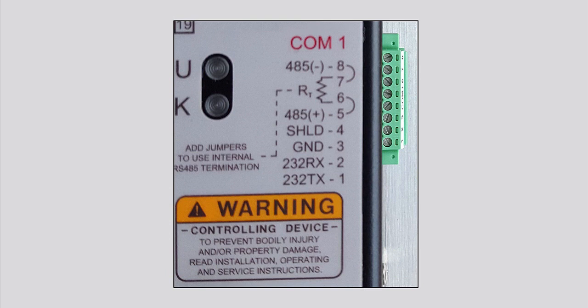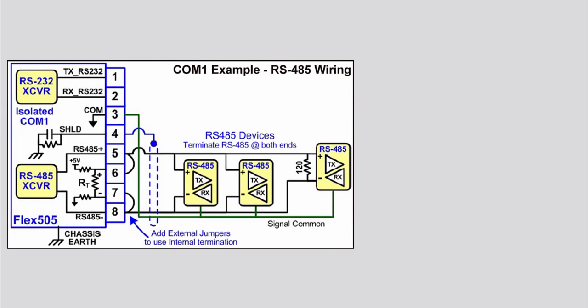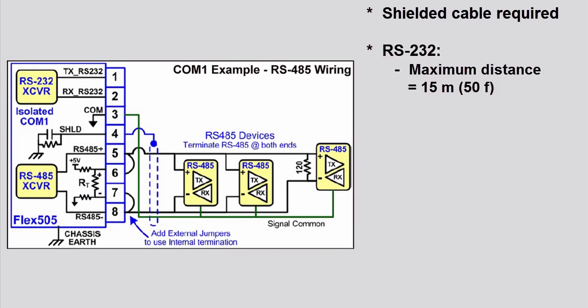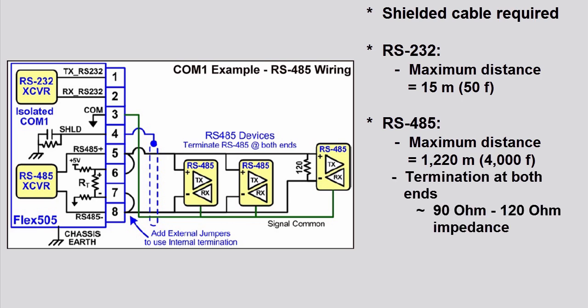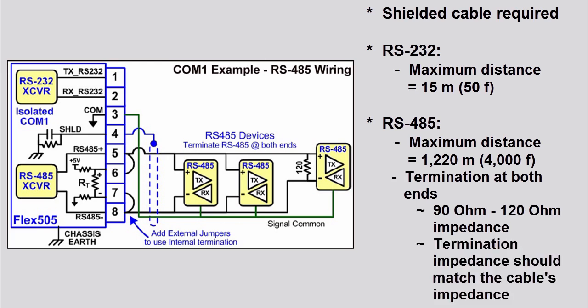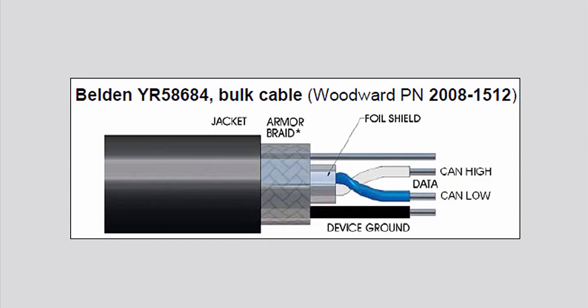The third available communication type is the serial port. An isolated RS-232 or RS-485 serial port is available for customer use. A shielded cable is required when using this port. Maximum distance for the RS-232 is 15 meters or 50 feet. Maximum distance for the RS-485 is 1,220 meters or 4,000 feet. RS-485 networks require termination at both ends with approximately 90 to 120 ohm impedance that matches the characteristic impedance of the cable used. The same cable used for CAN connections is recommended for serial connections.